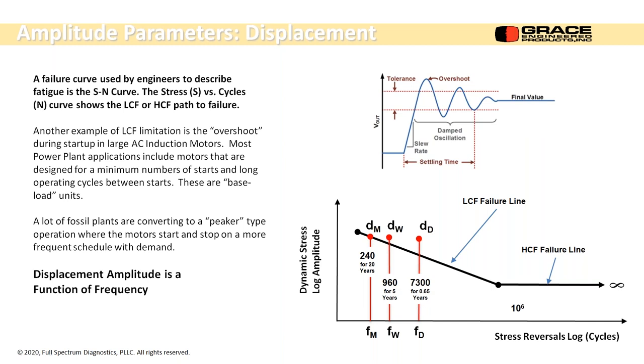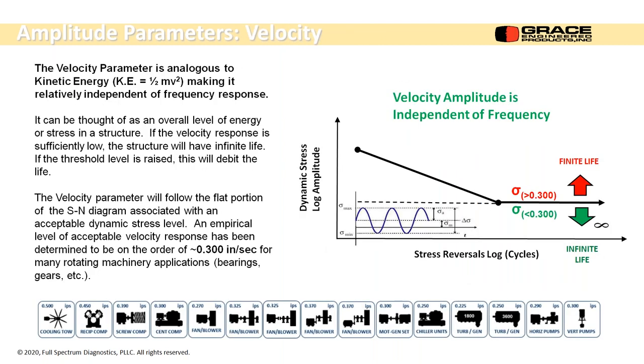Okay, so we haven't started seeing it yet, but the peaker type on-off stuff is going to be a big fatigue factor for big AC induction motors. Okay, and we can see how displacement amplitude is a function of frequency with this example as well. Okay, velocity. The velocity parameter is analogous to kinetic energy, which makes it relatively independent of frequency response. So if I suggest an alarm level of velocity, it's basically based on what I choose for my piece of equipment.